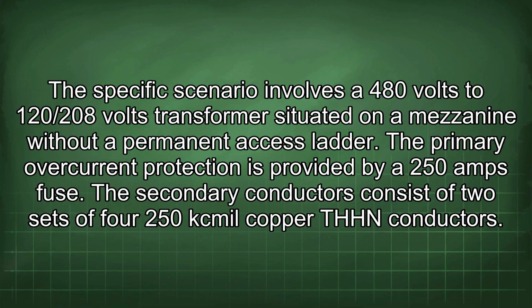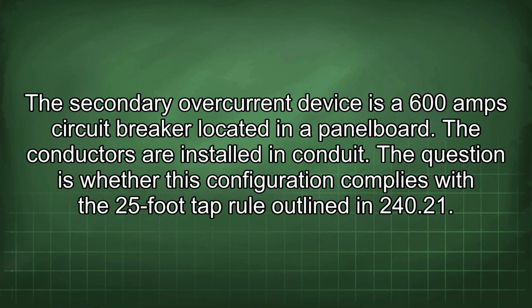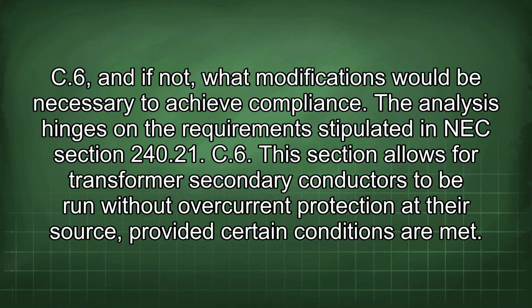The primary overcurrent protection is provided by a 250 amp fuse. The secondary conductors consist of two sets of four 250 kcmil copper THHN conductors. The secondary overcurrent device is a 600 amp circuit breaker located in a panel board. The conductors are installed in conduit. The question is whether this configuration complies with the 25-foot tap rule outlined in 240.21(C)(6), and if not, what modifications would be necessary to achieve compliance.